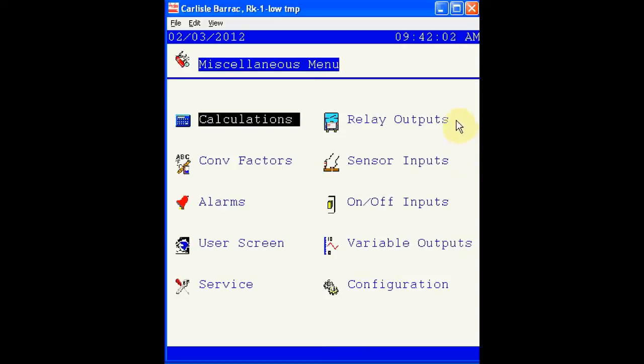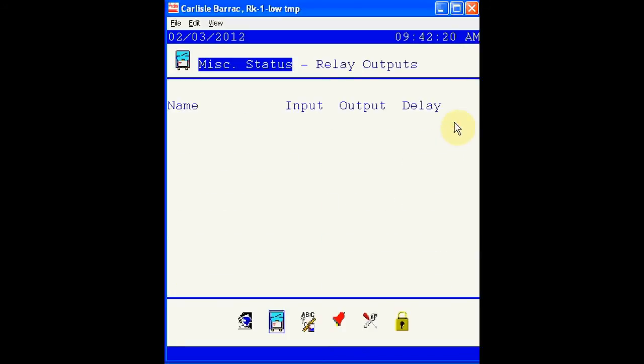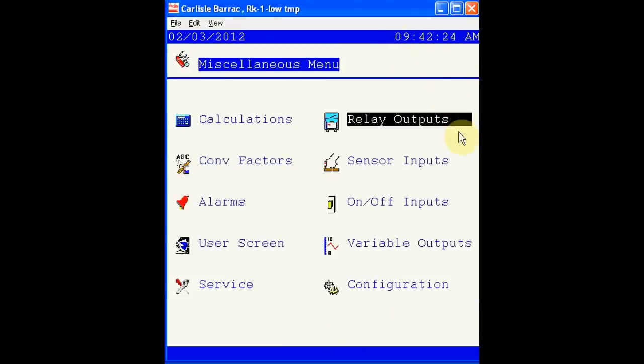The status for the miscellaneous menu can be viewed through any of these points. For instance, if we wanted to view the status of any relay outputs programmed through the miscellaneous menu, we would highlight this option. As you can see, no miscellaneous relay outputs are programmed. If we wanted to make changes in the miscellaneous menu, we would have to first select configuration.